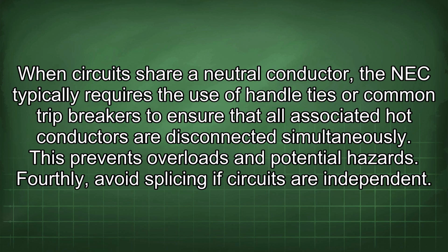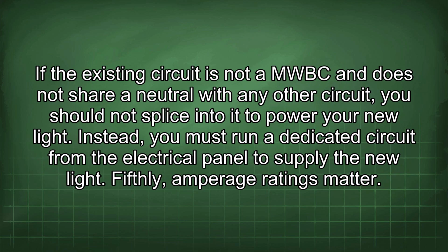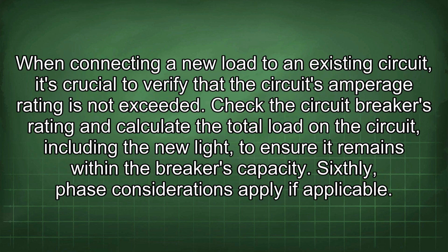Fourthly, avoid splicing if circuits are independent. If the existing circuit is not a MWBC and does not share a neutral with any other circuit, you should not splice into it to power your new light. Instead, you must run a dedicated circuit from the electrical panel to supply the new light. Fifthly, amperage ratings matter. When connecting a new load to an existing circuit, it's crucial to verify that the circuit's amperage rating is not exceeded. Check the circuit breaker's rating and calculate the total load on the circuit, including the new light, to ensure it remains within the breaker's capacity.